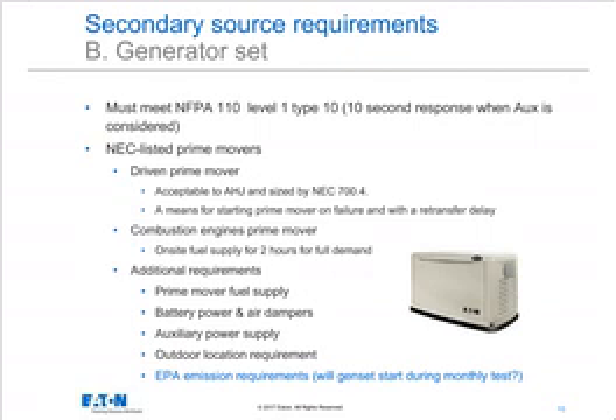So a couple of points here. NEC listed prime movers. If you're not familiar, prime mover is the NEC's word for motor. It needs to be acceptable to the authority having jurisdiction, sized per NEC 700, and I need a means for starting that motor on failure and with a retransfer delay, which means I need a battery so that I can start that motor by remote control or automatically when we sense a utility power failure. And before we come off of generator and back on to return to utility power, there needs to be a programmable delay. Why? So we can have a few minutes or seconds at least to make sure that the returned utility power is in fact going to remain on and stable.